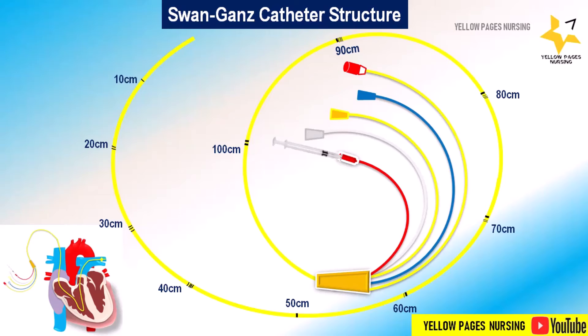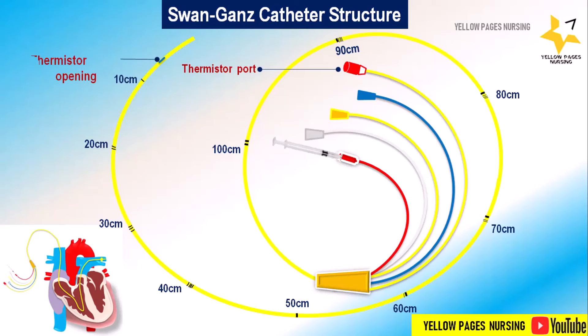The end at 100 centimeters is highlighted with two thick lines. Next is the thermistor. The pulmonary artery catheter has a thermistor device approximately three to five centimeters from the tip. The thermistor measures temperature and allows calculation of cardiac output by the thermodilution technique.